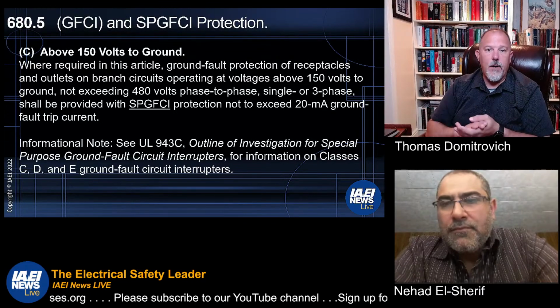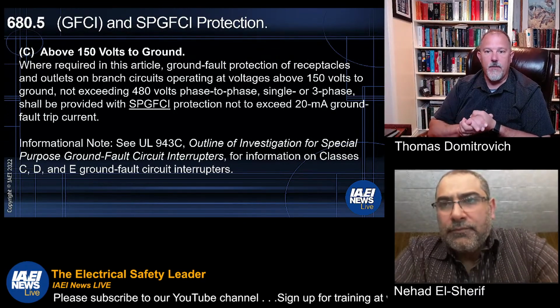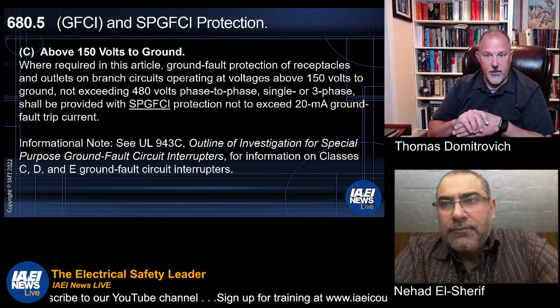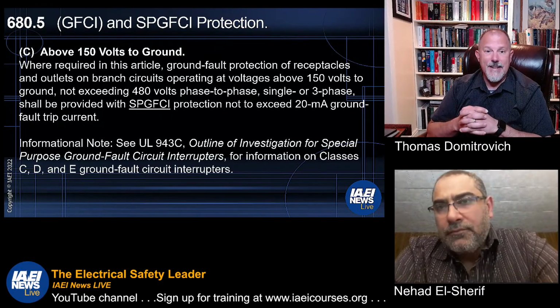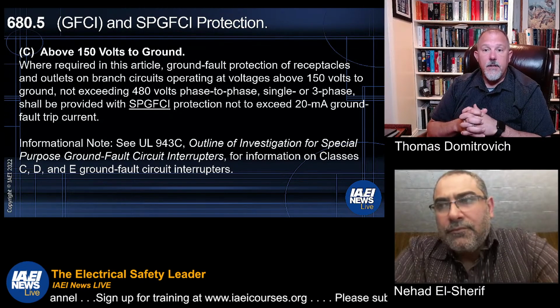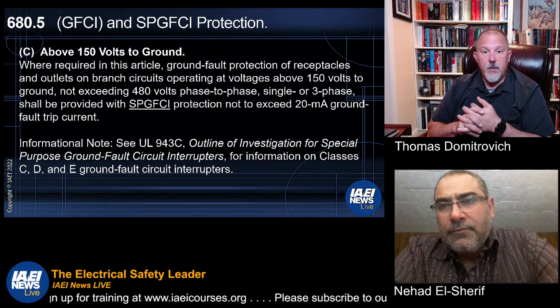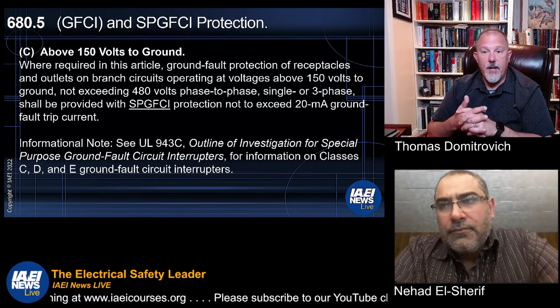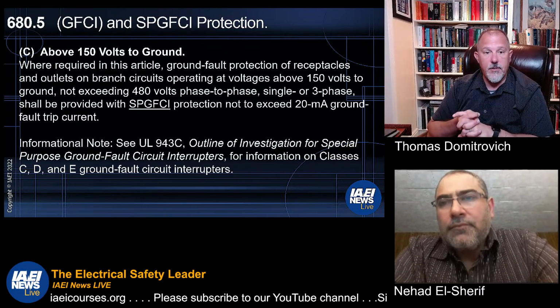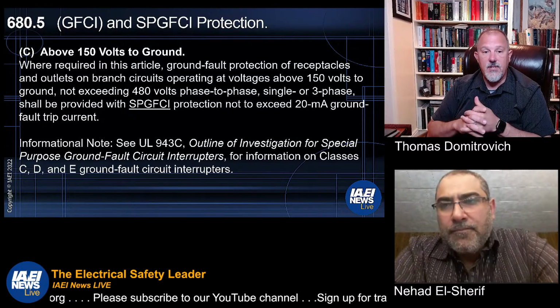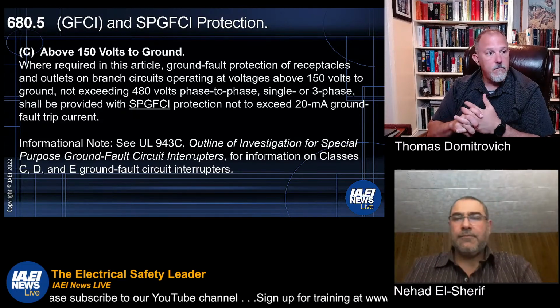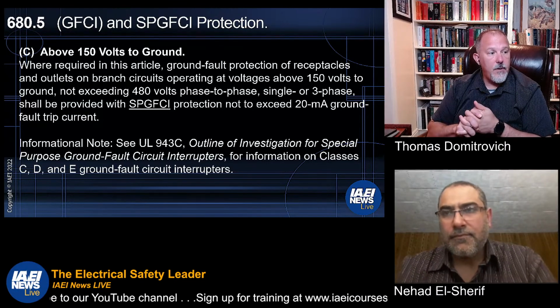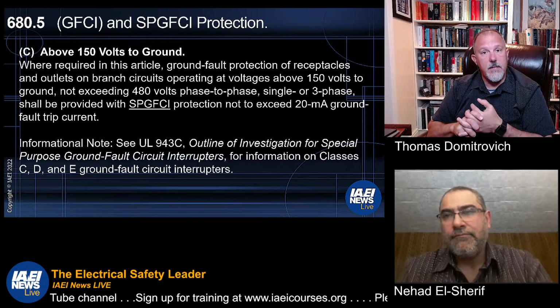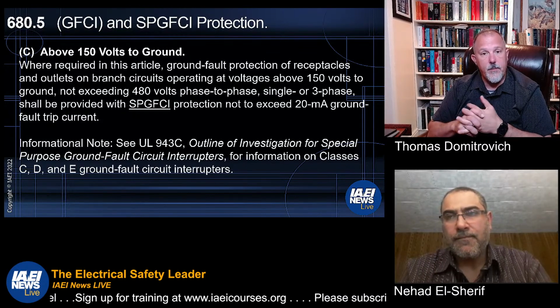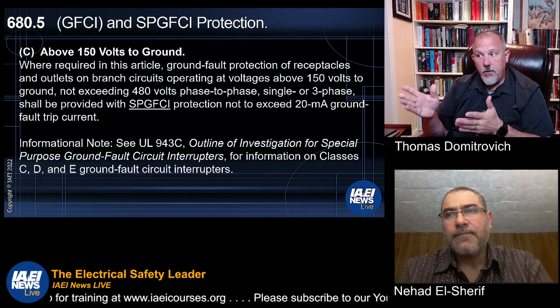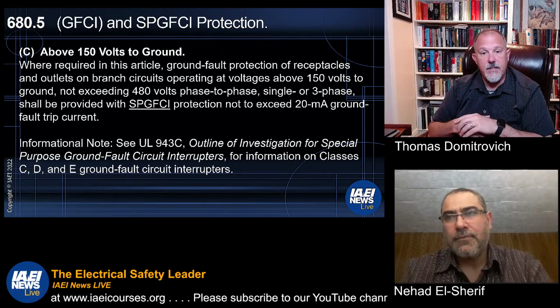Now, (C) says, where required in this article, ground fault protection of receptacles and outlets on branch circuits operating at voltages above 150 volts to ground, not exceeding 480, single phase or three phase, shall be provided with special purpose GFCI protection not to exceed 20 milliamps. There's that 20 milliamp number that you had noticed. And they reference the 943C outline of investigation. And then 680.6 tells us that all of the equipment in these swimming pool areas has to be listed. So you've got to have a special purpose GFCI listed to 943C.